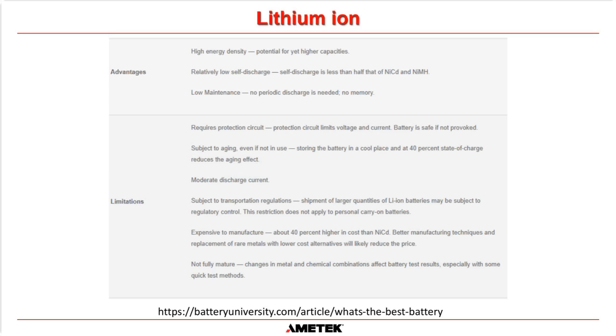So at this moment in time, there are no maintenance recommendations for lithium-ion batteries whatsoever, which is why a lot of plants are looking into them now, because obviously the maintenance costs for a lead-acid battery are quite high, because you have to follow the IEEE regulations to maintain them. Especially if you're a NERC plant, you've got to follow NERC as well. But with lithium-ion, you don't have to do any maintenance on it. It's all done by the battery monitoring system inside the lithium-ion itself. There's nothing you can do to that battery for maintenance.